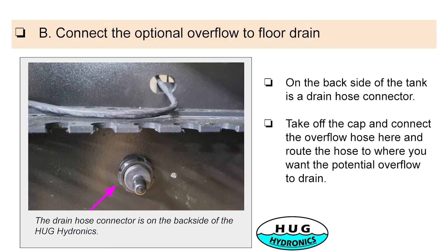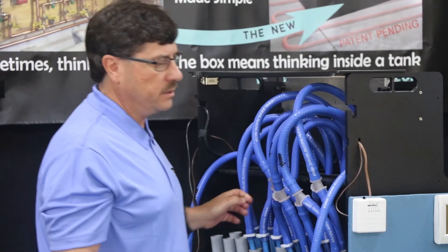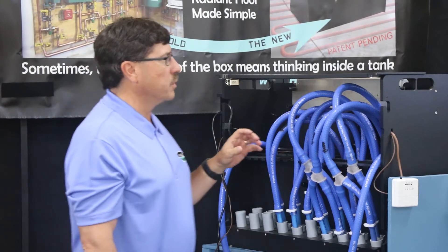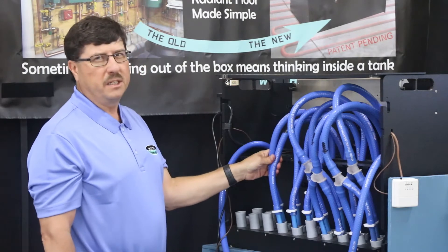The next step is to hook up. There's an optional drain port on the back of the unit — we can show you that later, but it's just near the back of the system. You connect that to the drain and connect it to your overflow. The next step is to connect the source and return hoses to the PEX pipes. The hoses come out of the unit and connect up to the PEX coming out of the floor. You have flow in and a return for each of the PEX lines, and you trim the hoses just enough so when you get it closed up, you get a nice clean look.